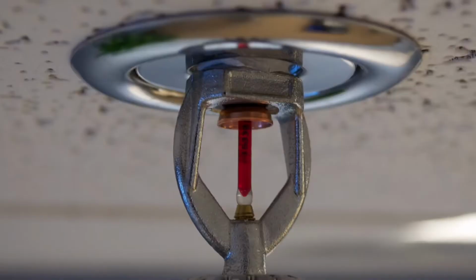Next is the wet riser system. It is designed according to the requirements of the Fire and Rescue Department of Malaysia. There are a total of 3 wet risers on each floor, and landing valves are in protected areas such as fire escapes, stairs and lobbies. Lastly is the automatic water sprinkler system. It's installed throughout the building except rooms that contain high voltage electrical equipment, such as the fire control room and electrical room. Next, the non-water based system consists of the AeroHub green aerosol fire suppression system and portable fire extinguishers.